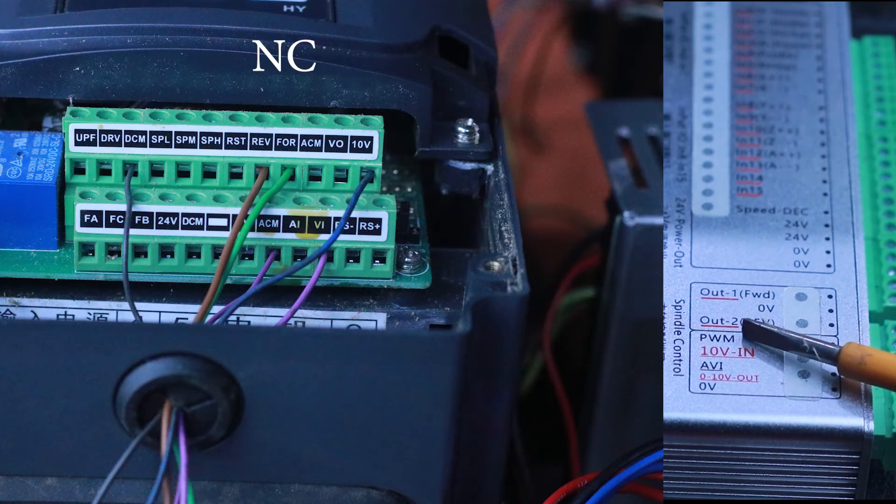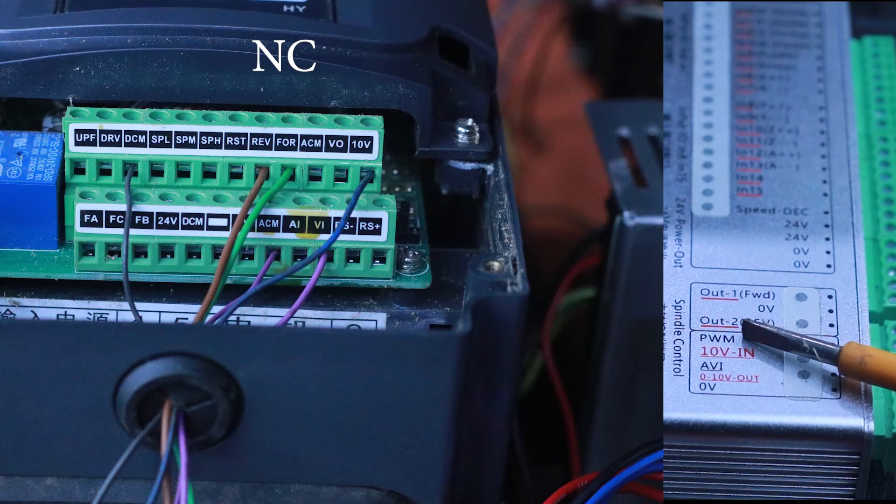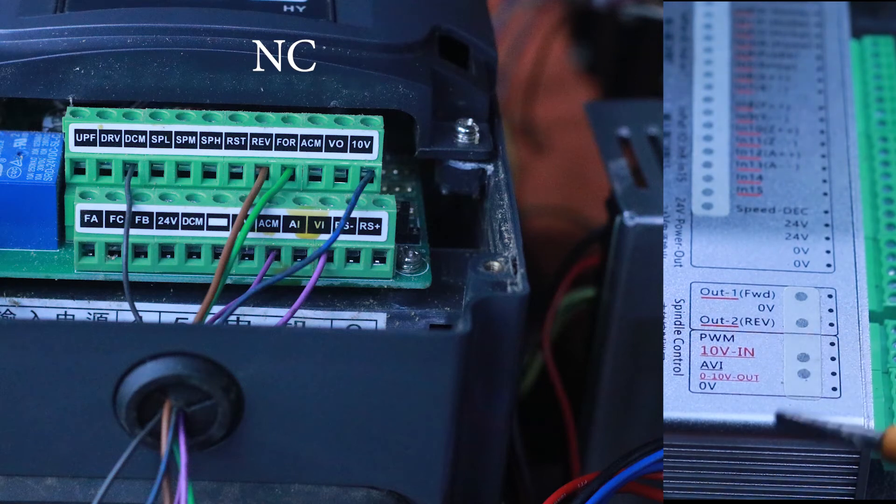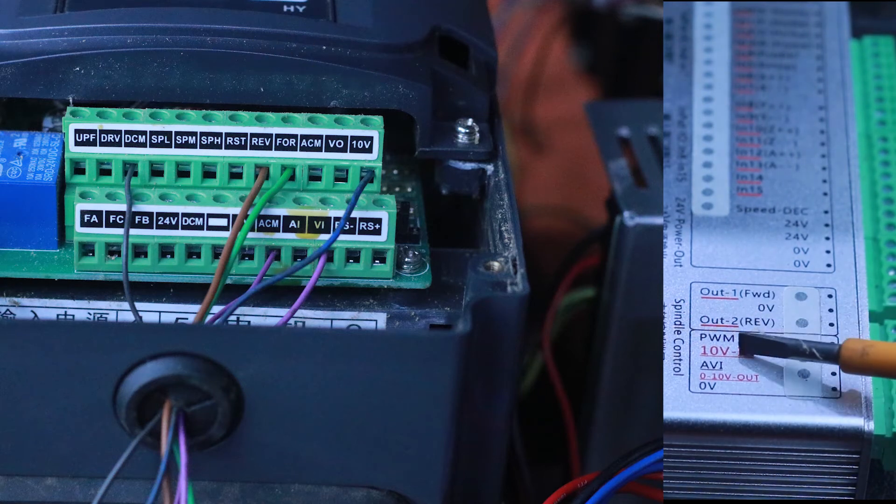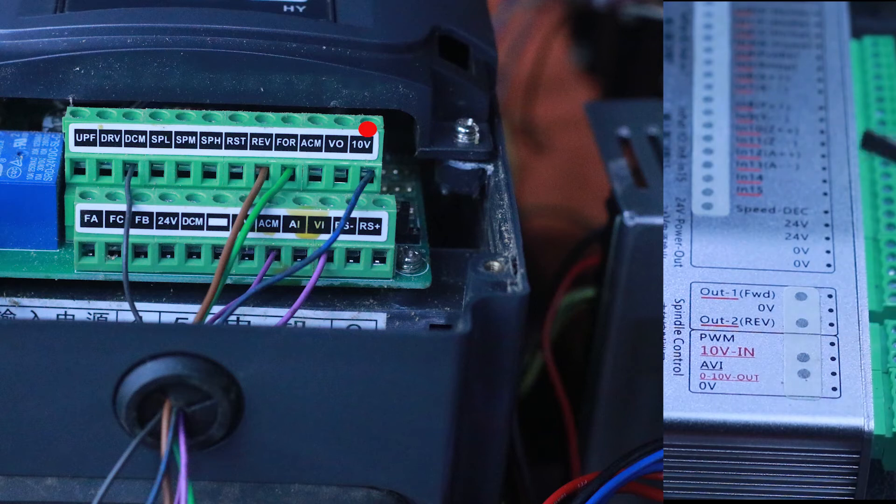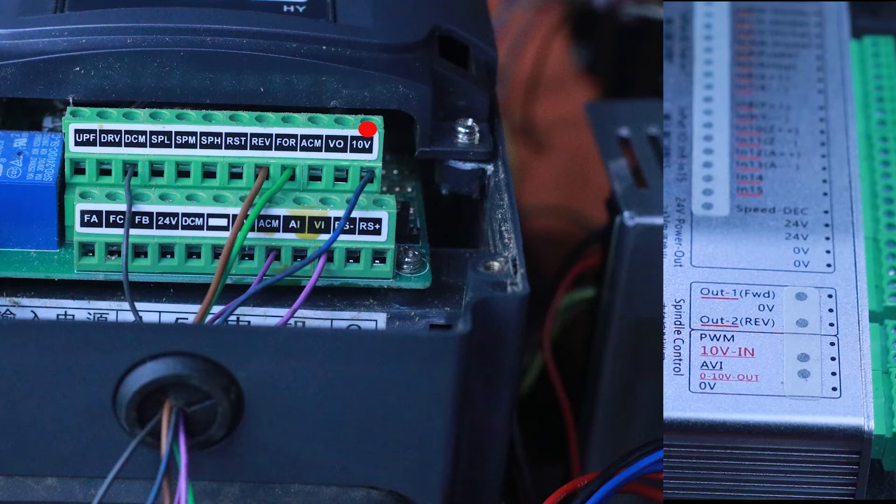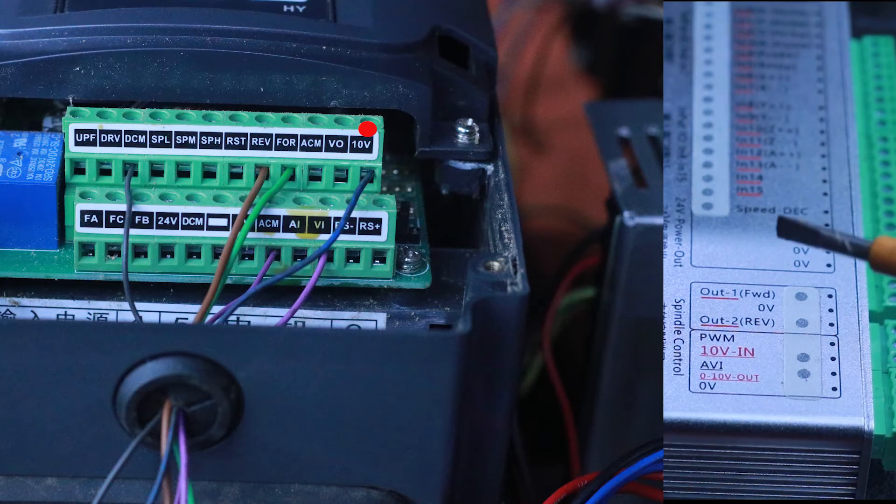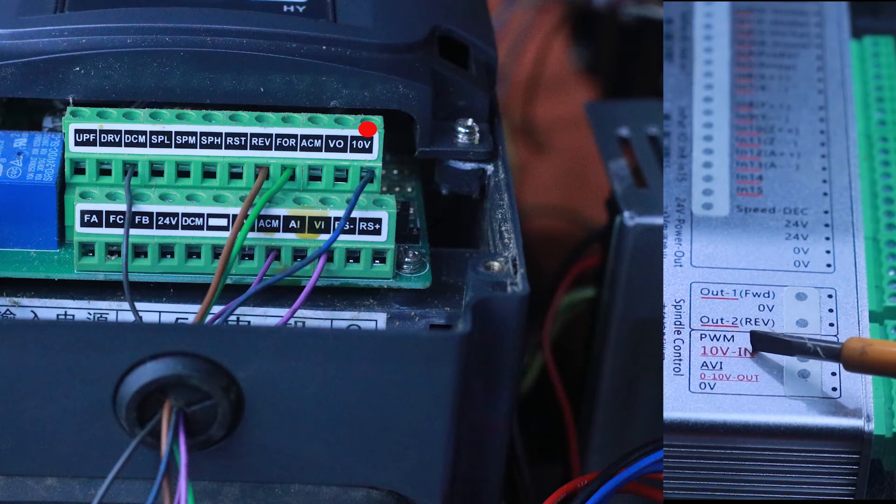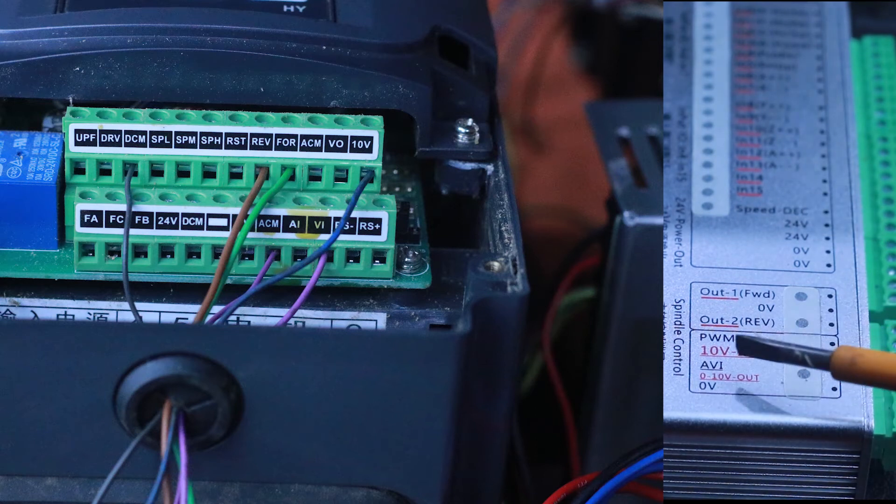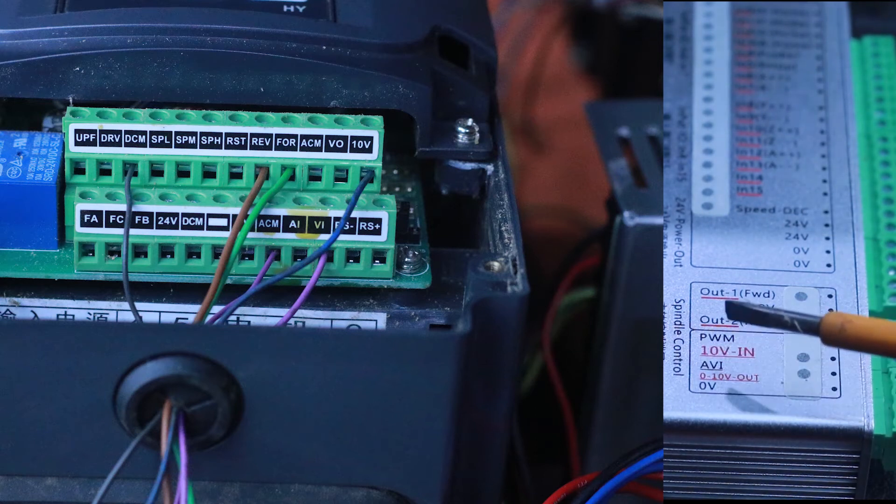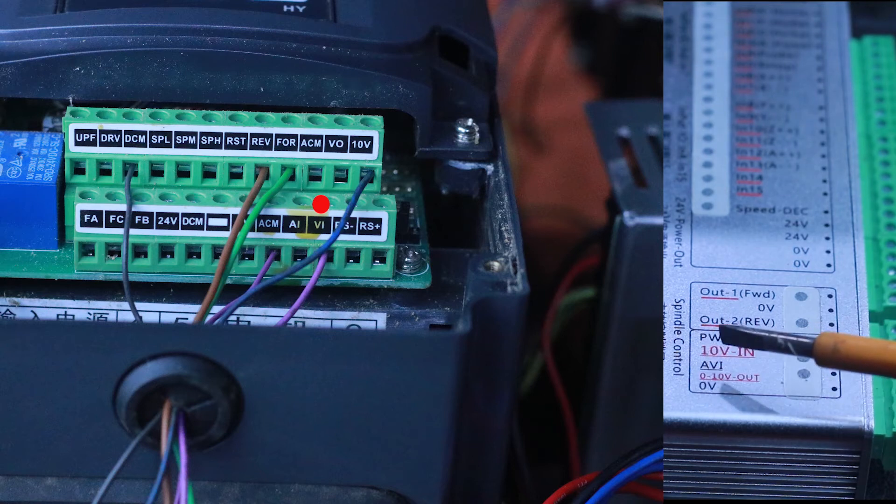The PWM is non-connect so we don't connect this one. We have 10 volt in—this 10 volt in takes voltage from the VFD. The 10 volt from that VFD comes to this 10 volt in on this controller. We have the AVI which is the variable voltage from 0 to 10 volts, which goes to the VI pin on the VFD.